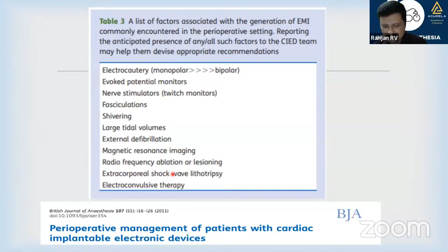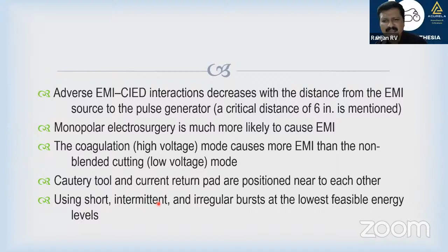Okay, so how can we prevent it? The simple thing is, the EMI and CIED interaction decreases as the distance increases. If it is more than 15 centimeter or more than 6 inch, the chance of EMI is very less. Monopolar is more likely to cause it. Okay, coagulation mode causes more EMI compared to the cutting. Okay. If the cautery tool and current return pad are positioned very near to each other, then EMI is very, very less. Using short, intermittent, irregular bursts at the lowest feasible setting prevents EMI.